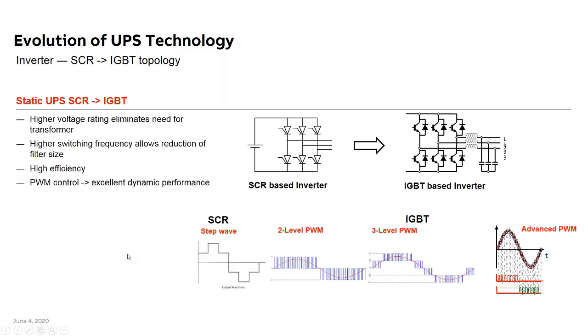Over the years, we have gone from better semiconductors becoming available, from the SCR to bipolar transistors and now to IGBTs. An IGBT is a transistor, a device that we can actually switch on and off very fast as needed. And UPSs today are based on what we call PWM, pulse width modulating control, where instead of just having a step wave or a square wave like with the SCR, we're still switching between a positive and a negative on the DC side. But with very fast switching, there's a pulse train where the pulse width is regulated so that it's as close to an ideal sine wave as possible.